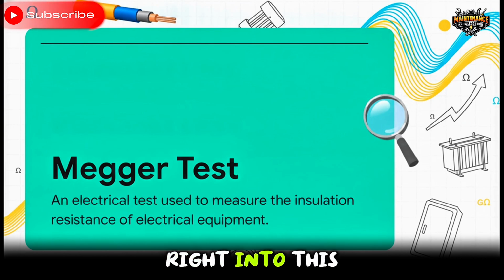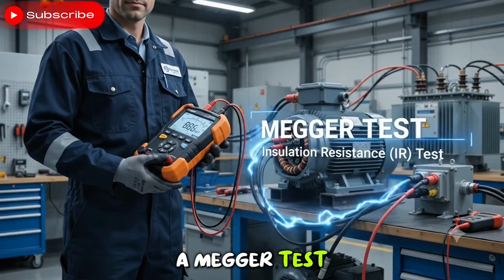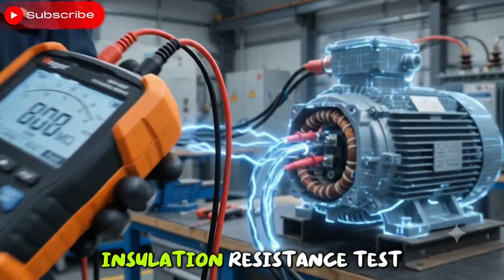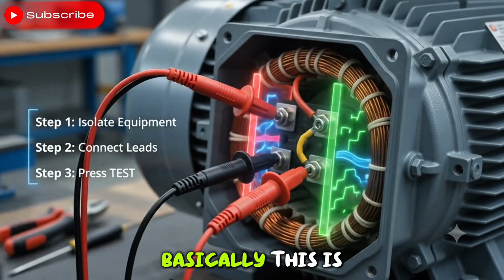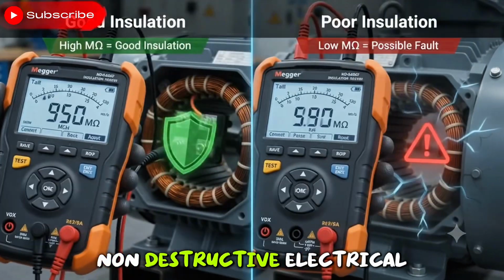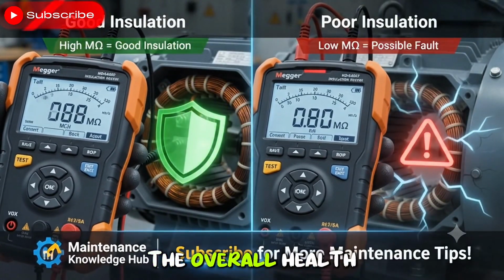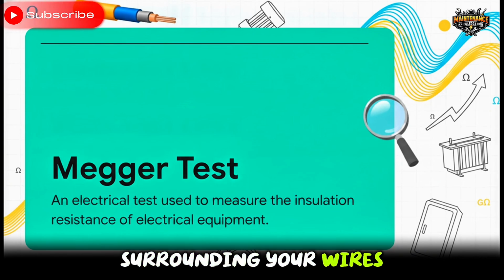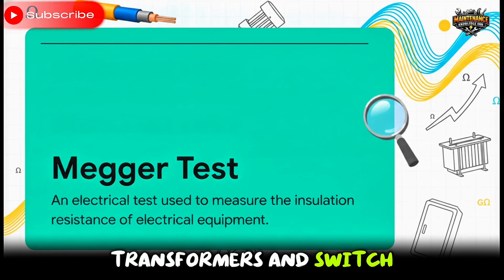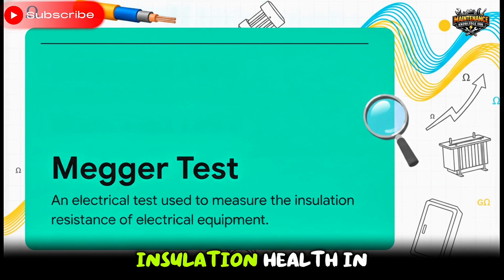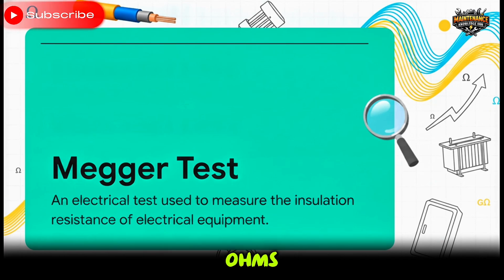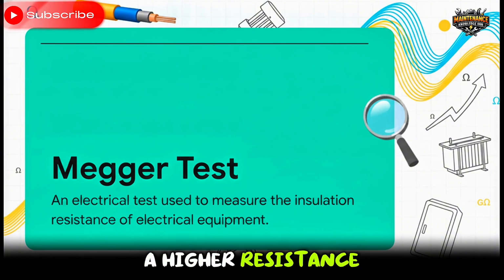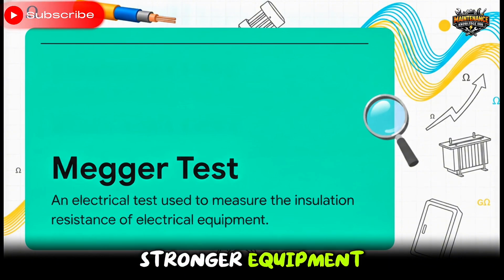Okay, let's dive right into this. To combat this invisible threat, engineers and technicians rely on what's widely known as a Megger test, or, if we're being formal, an insulation resistance test. Basically, this is a dedicated, non-destructive electrical test used to measure the overall health of the insulation surrounding your wires, motors, transformers, and switchgear. We measure this insulation health in units called megaohms or gigaohms. The simple, golden rule you need to remember here is, a higher resistance number indicates healthier, stronger equipment.